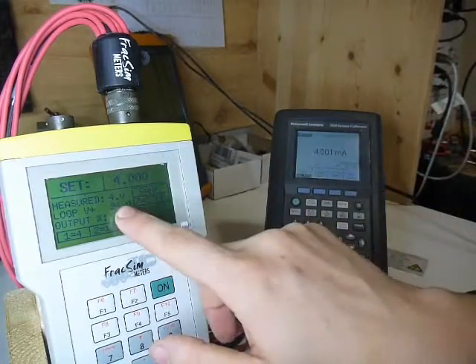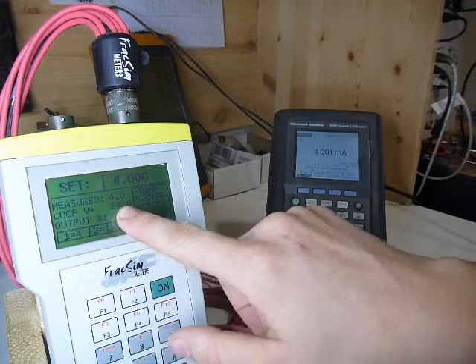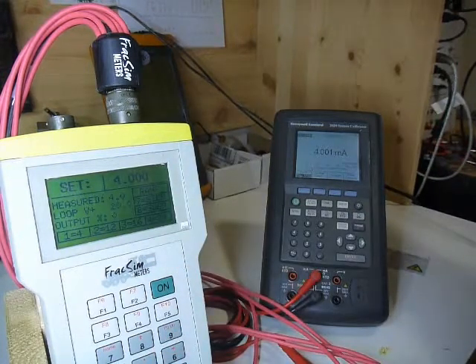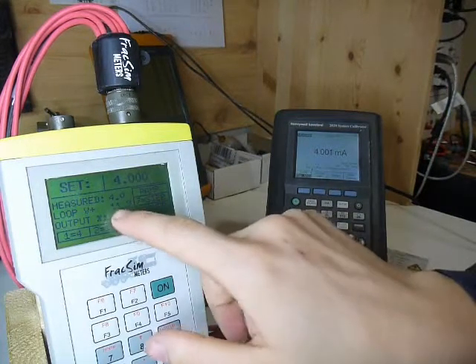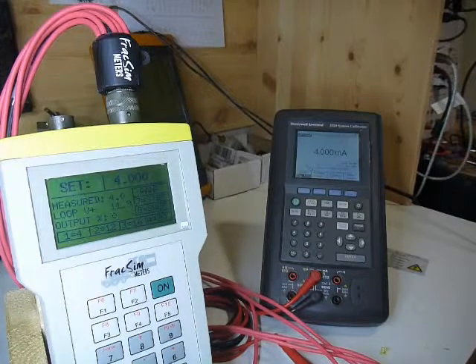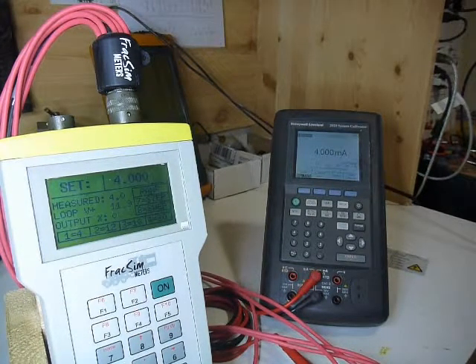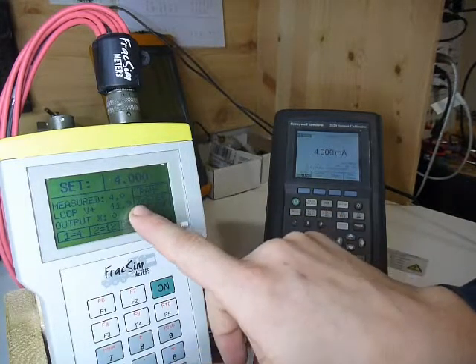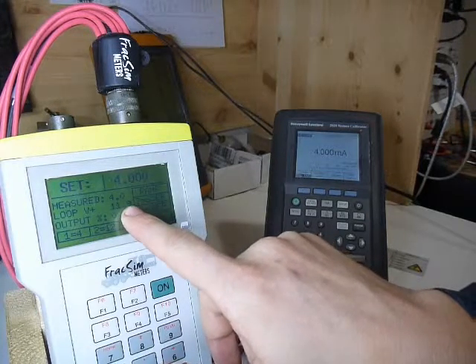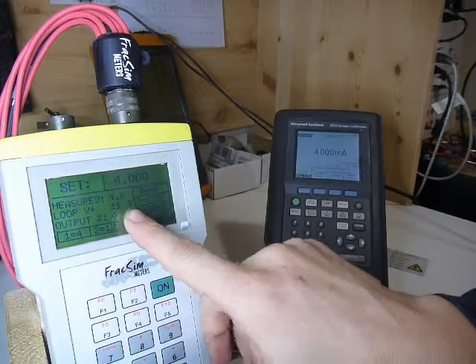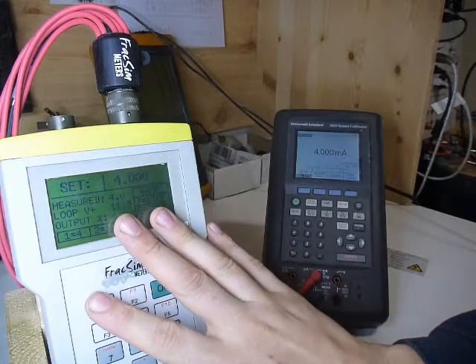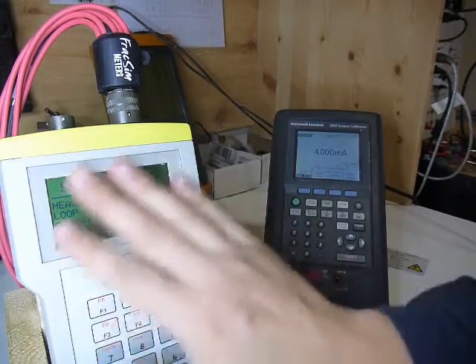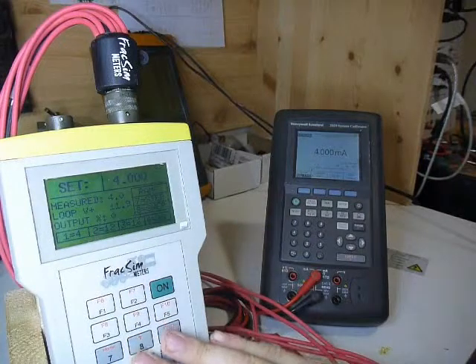Now this time, this loop voltage actually shows what's on the power supply. So if I turn my bench power supply down to 12 volts, it shows you that. And it's important when you're troubleshooting a current system. If you are working on a unit and there's a known loop supply, it's important that this is correct. If you, for example, know that the loop should be at 24 volts and you got 12 volts, there's a serious issue there. And the thing is, your simulator might work correctly, but the unit might not, because the electronics in this are powered by batteries.